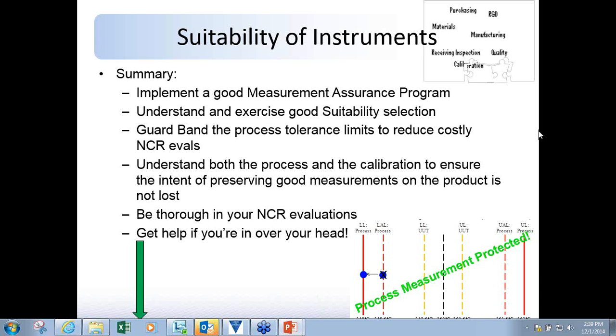Guard band the process tolerance limits to reduce your nonconformance reporting evaluations, and understand both the process and the calibration to ensure the intent of preserving good measurements on the product is not lost. When you find out-of-tolerance situations for your instrumentation, be sure that you're doing out-of-tolerance investigations, nonconformance reporting investigations. And if you need help in how to do that correctly and have the correct forensic mindset to find the right root cause and get to the right solution, get help if you're in over your head. We're here to help, and we offer consulting services to help you with those reviews.